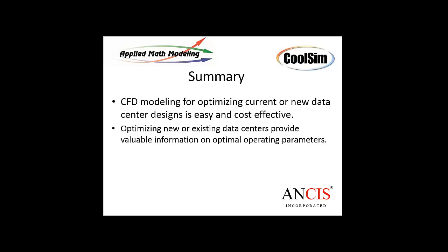Here's a question. Based on average watts per rack, how many adjustments are required to get the model correct? Not that many. Again, it's a guide. It depends if the rack is blanked or not. If the rack is blanked, so there's not a lot of leaking, and there are no holes between the servers, then average watts per rack is pretty good.